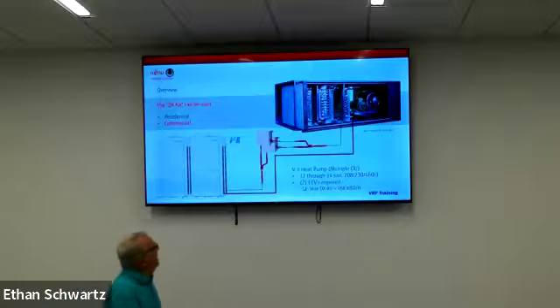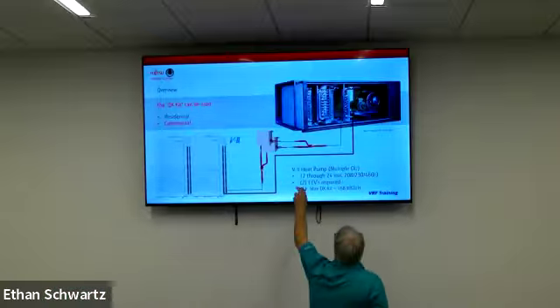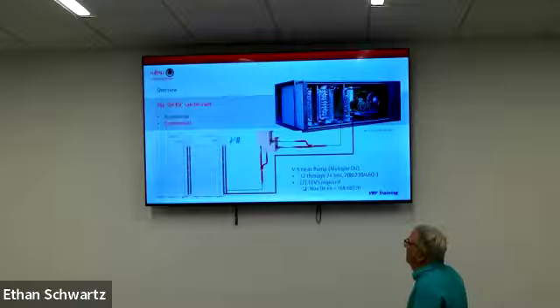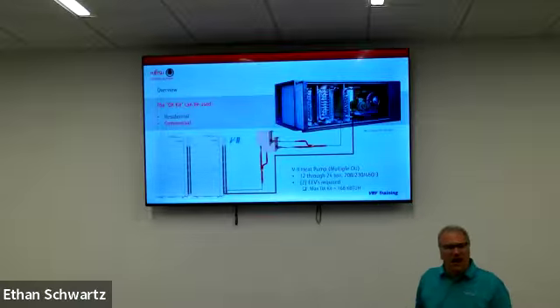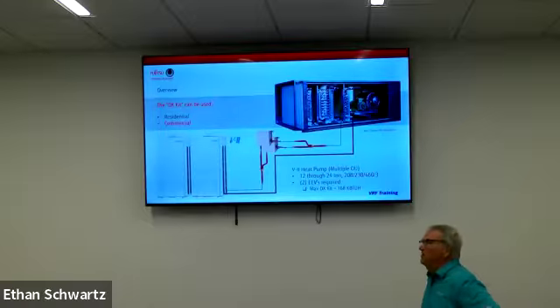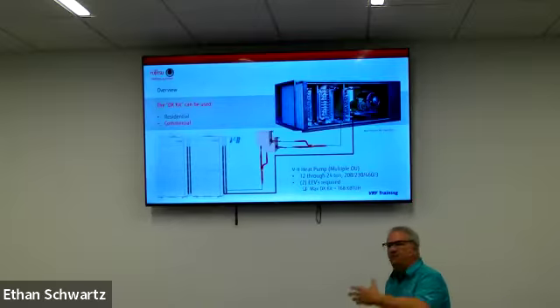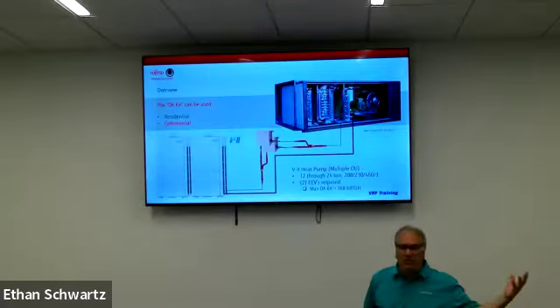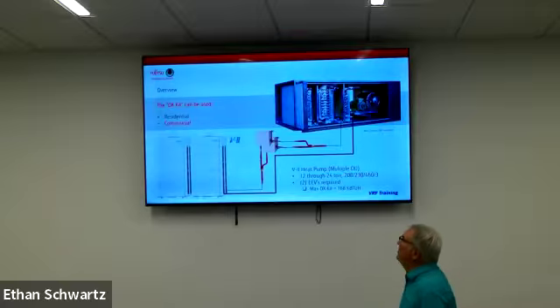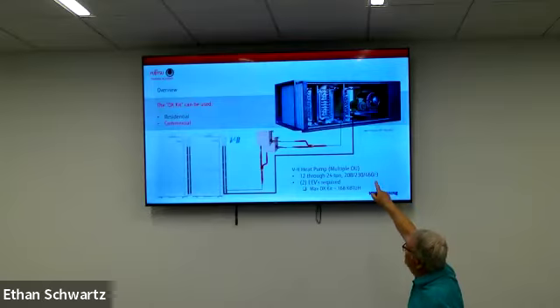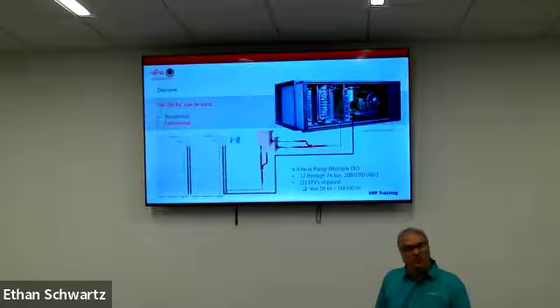You go bigger, then we can put multiple electronic expansion valves to pipe to the unit. Everybody kind of see how that would work? So if your contractor says, yeah, we got this 40-ton unit, it's down, and you guys are 8 weeks out, well, you can still have all the same functionality, but not using the compressor section, and use our units and turn it into a heat pump as well, although you wouldn't have to use heating if you choose.